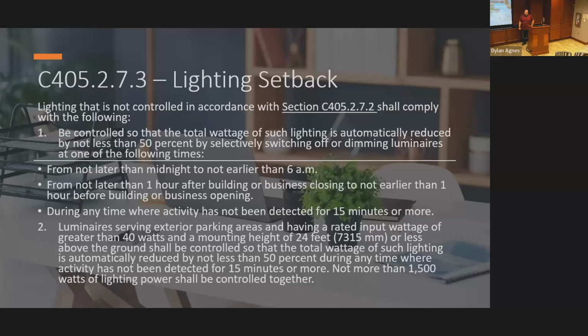I recommend having the highest sensitivity for your occupancy sensor if you do this, or if you're required to do this, and to stay at 50% and go to the maximum of 50. Like, don't try to be energy efficient on this part. In my opinion, this area of energy efficiency is misguided, butting up against occupant comfort and safety.